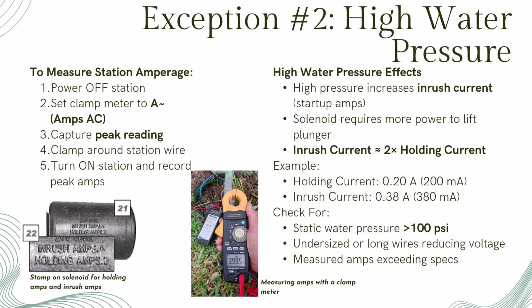When water pressure is too high, the solenoid has to work harder to open the valve. That extra effort shows up as an increase in inrush current, the short burst of amps needed to lift the plunger. The solenoid then settles into a lower holding current once the valve is open. For most valves, the inrush current is about twice the holding current.